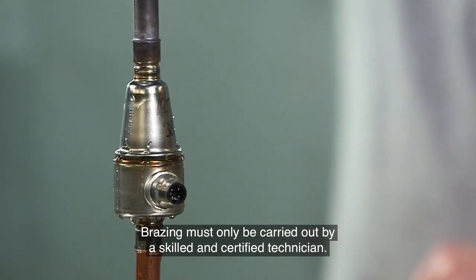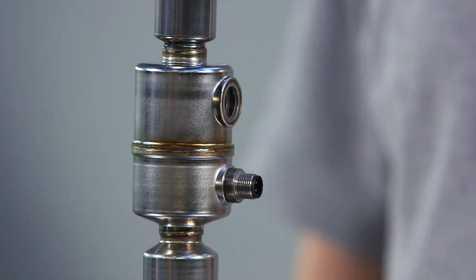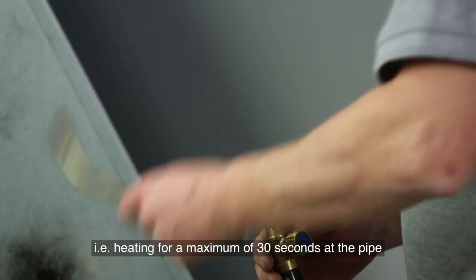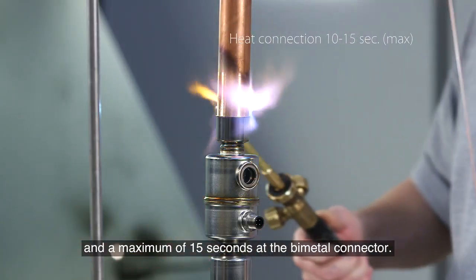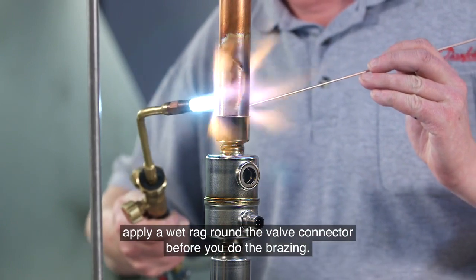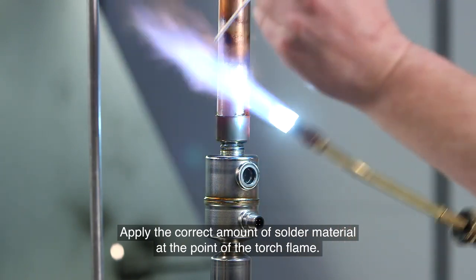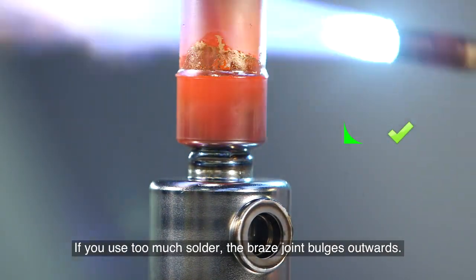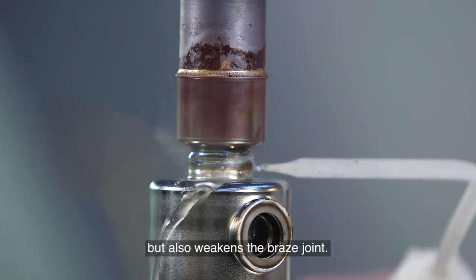Brazing must only be carried out by a skilled and certified technician. The main steps for a bigger unit are the same, but you use a bigger torch size. You still stay within the same time limits — heating for a maximum of 30 seconds at the pipe and a maximum of 15 seconds at the bimetal connector. If the conditions mentioned in the braising procedure cannot be met, apply a wet rag around the valve connector before braising. Apply the correct amount of solder material at the point of the torch flame — you should be able to see the typical so-called ski slope. If you use too much solder, the brazed joint bulges outwards, which wastes money, harms the environment, and weakens the joint.